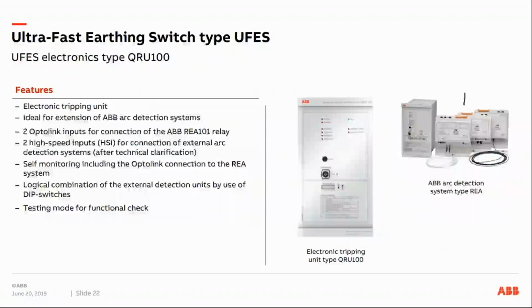The other option would be the UFES electronics type QRU100. That one is an electronic tripping unit only. It's ideal for complex systems and for an extension of ABB's arc detection systems, the REA family. It has 2 Optolink inputs for the connection of the ABB REA101 relay, and 2 high-speed inputs for the connection of external arc detection systems. It is self-monitoring and has also a logic combination of the external detection units by the use of dip switches. That one also has a testing mode for functional checks.